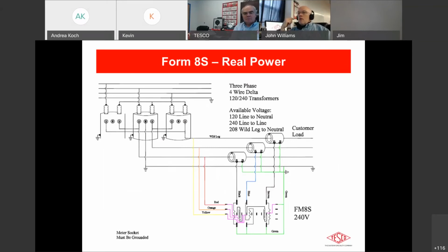In the 8S situation, we have a transformer rated meter here again. In this case, we show the 3 CTs, and this is a 4-wire delta. So we have a high leg. This diagram is called the wild leg. So we have a 208 from the wild leg down to neutral. Then we have 240 line to line and 120 line to neutral from the other 2 phases. So this is the transformer rated application.